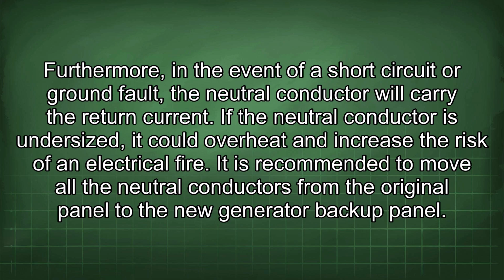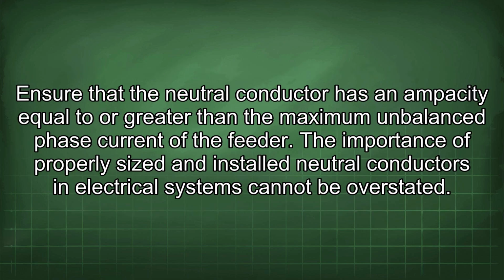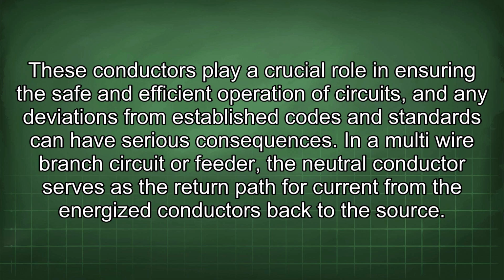It is recommended to move all the neutral conductors from the original panel to the new generator backup panel. Ensure that the neutral conductor has an ampacity equal to or greater than the maximum unbalanced phase current of the feeder. The importance of properly sized and installed neutral conductors in electrical systems cannot be overstated. These conductors play a crucial role in ensuring the safe and efficient operation of circuits, and any deviations from established codes and standards can have serious consequences.